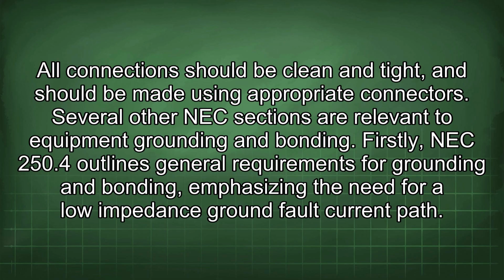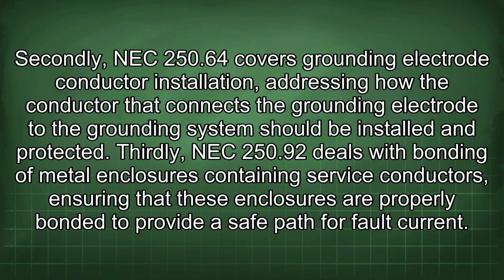Several other NEC sections are relevant to equipment grounding and bonding. Firstly, NEC 250.4 outlines general requirements for grounding and bonding, emphasizing the need for a low-impedance ground fault current path. Secondly, NEC 250.64 covers grounding electrode conductor installation, addressing how the conductor that connects the grounding electrode to the grounding system should be installed and protected.